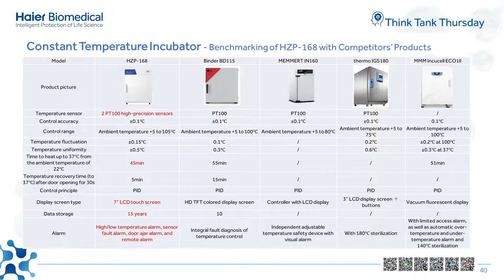For HZP-168, we also have 2 PT100 high-precision sensors, but other products only have 1. For the temperature fluctuation, we have plus and minus 0.15 degree. And for temperature uniformity, we have plus and minus 0.5 degree. And for the temperature recovery time, after a door opening of 30 seconds, we only use 2.5 minutes. And for other products like Binder BD115, it takes 5 minutes. And we also have a 7-inch LCD touchscreen in our product and 15 years data storage and many kinds of alarms.